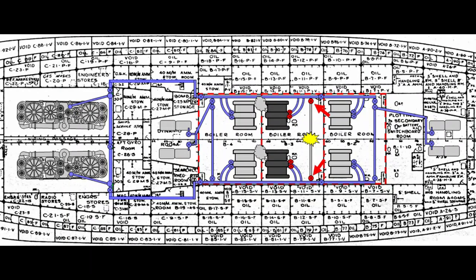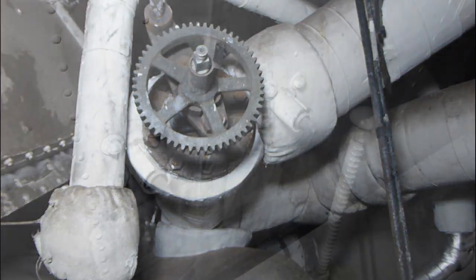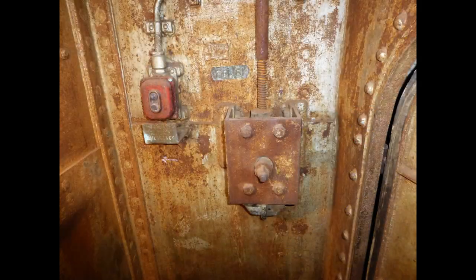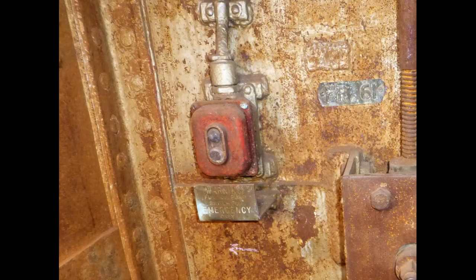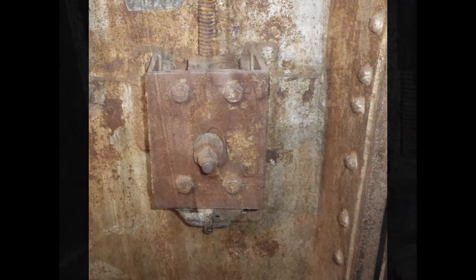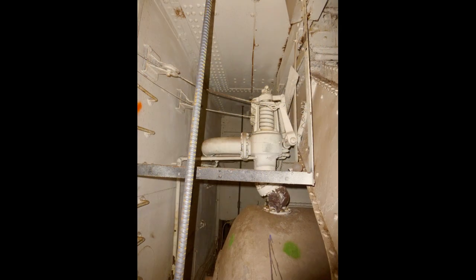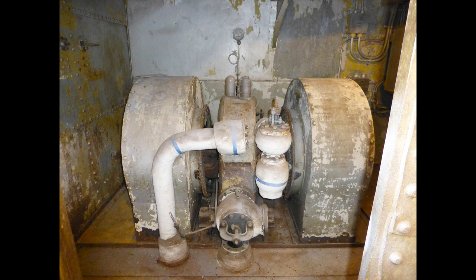What if 412-degree steam from a major pipe rupture inside a boiler room makes it uninhabitable? As the crew evacuates the room, stop valves are closed to isolate both boilers. Fuel pumps and boiler fuel feed are shut off with remote quick-acting valves, and relief valves are opened to release boiler pressure through the smokestack. Forced draft blowers push fresh air into the room, and heat and steam are pushed out through the boilers and up the stack. Once cleared, crew can re-enter the room to make repairs.